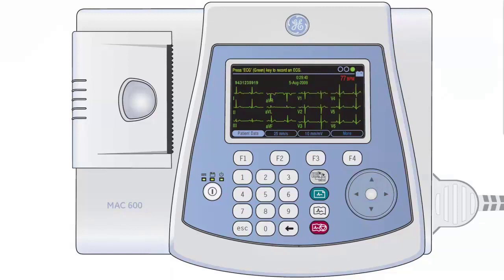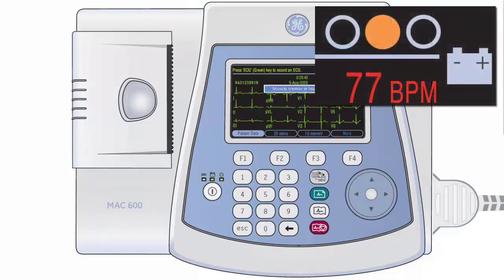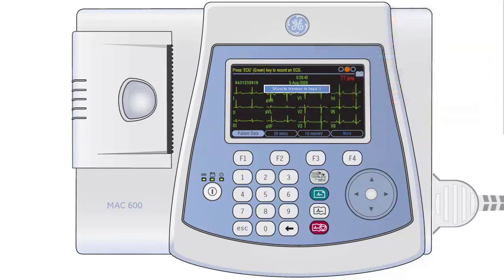An orange indicator means that there is poor connection to the patient, which is likely to cause some interference on the ECG. You should check the leads indicated and confirm the electrodes have not slipped out of position and that the patient is relaxed.